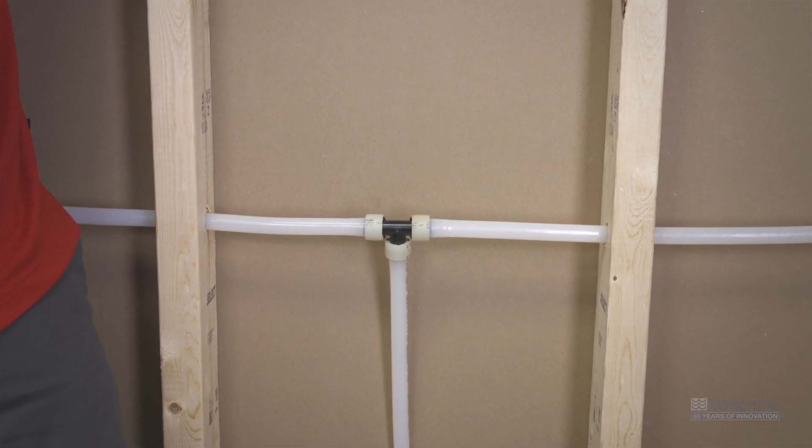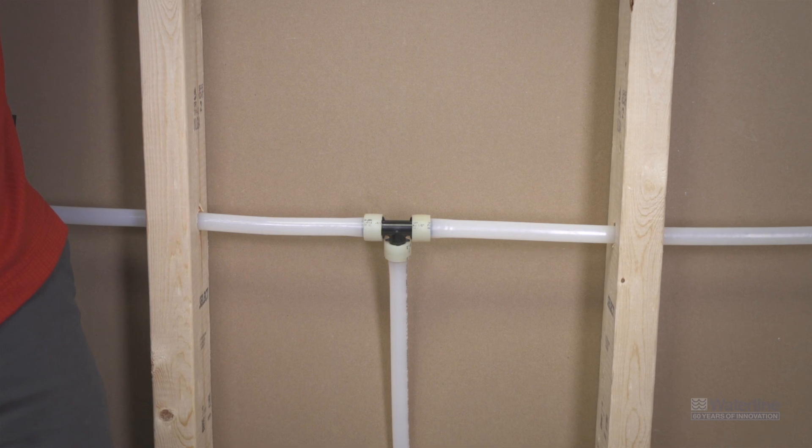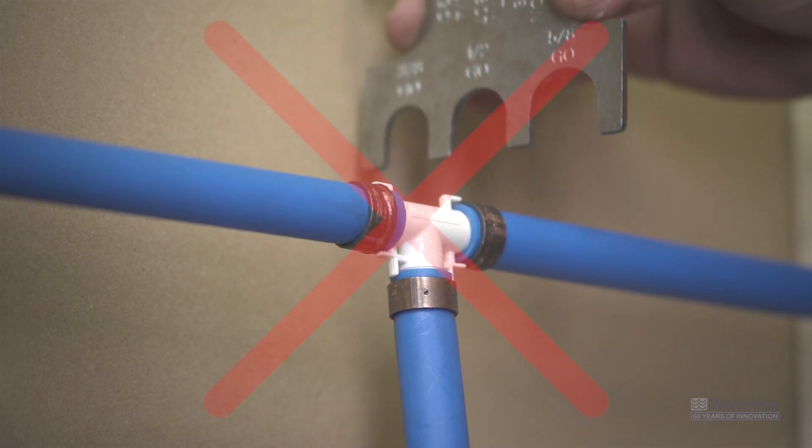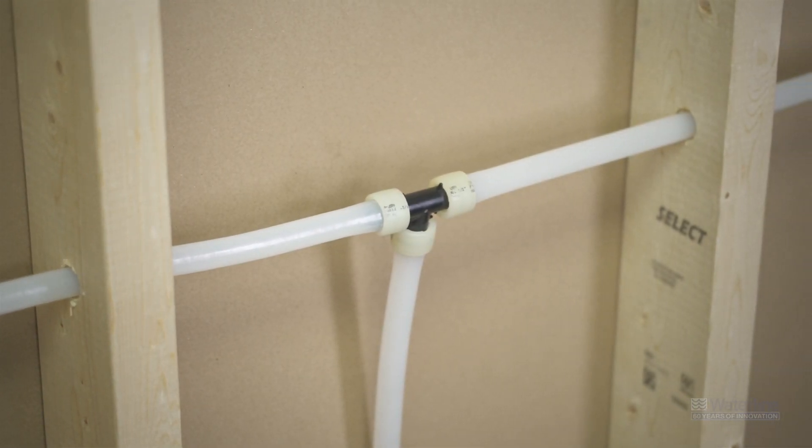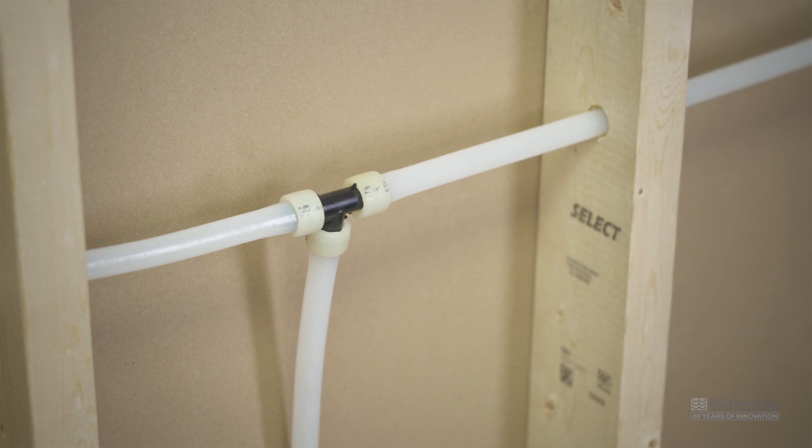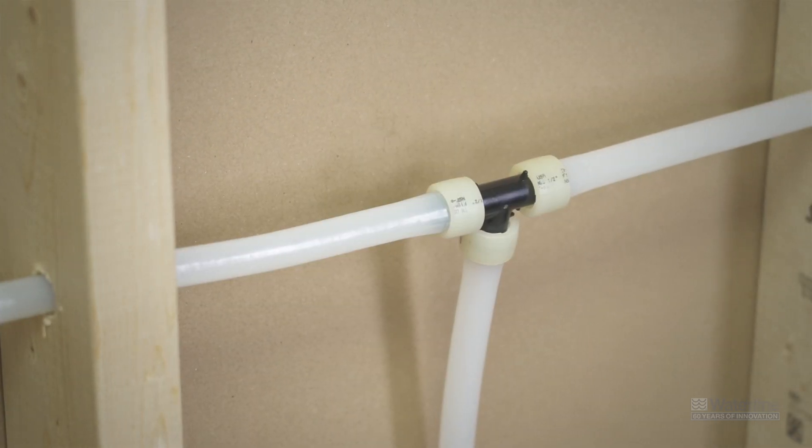Secondly, since the PEX pipe and rings constantly shrink to the original size, your cold expansion connection actually continues to strengthen over time. Finally, there is no need to use a go no-go gauge since a cold expansion connection is purely visible. So you can tell if the connection has failed or if it was successful simply by seeing if the ring is touching the fitting shoulder.